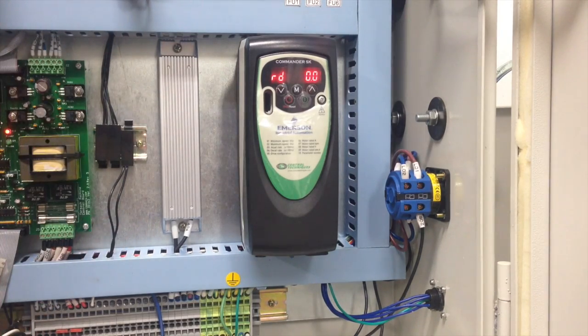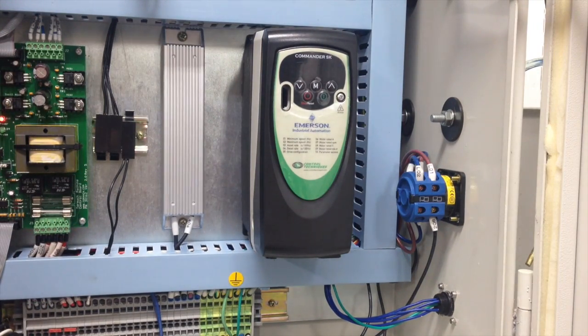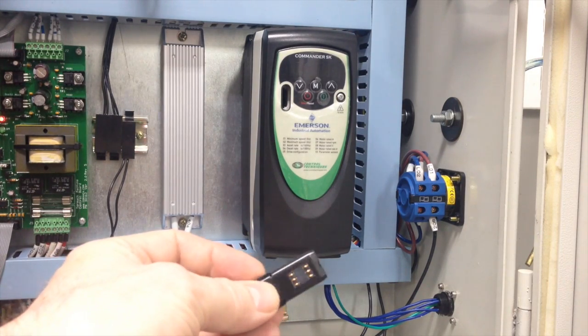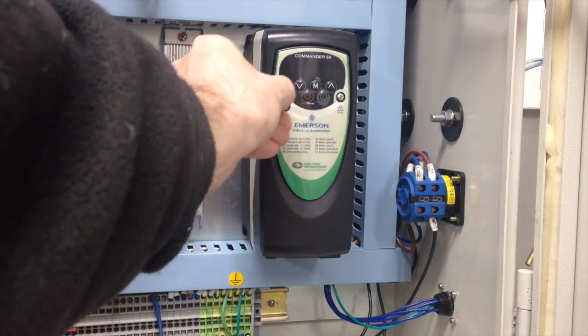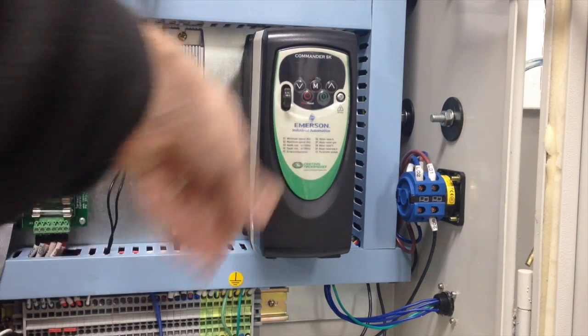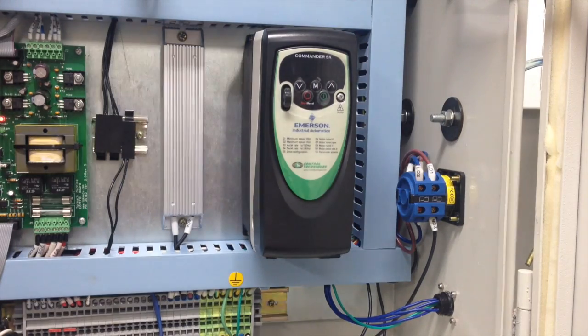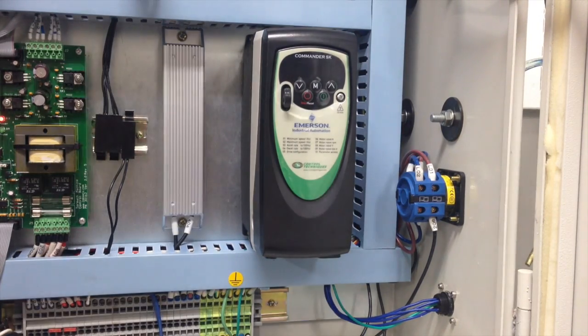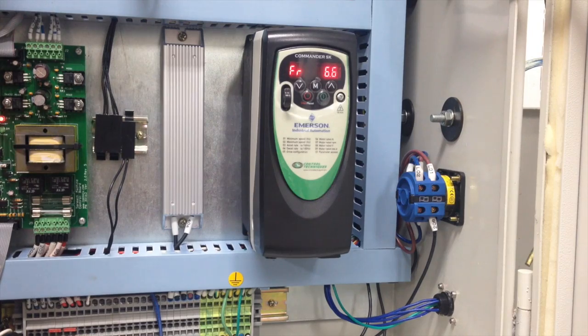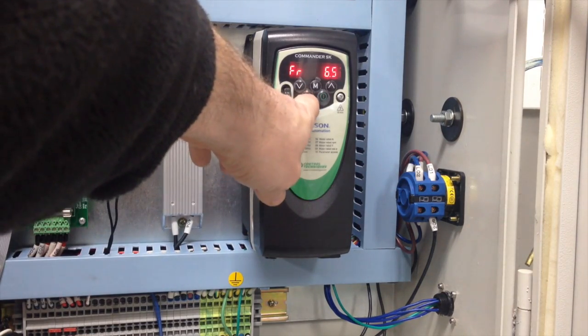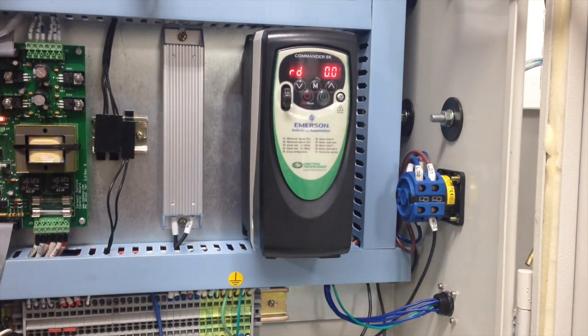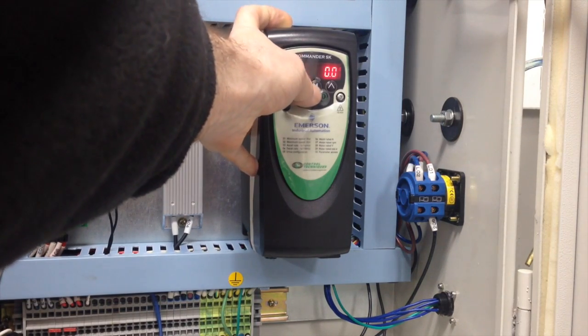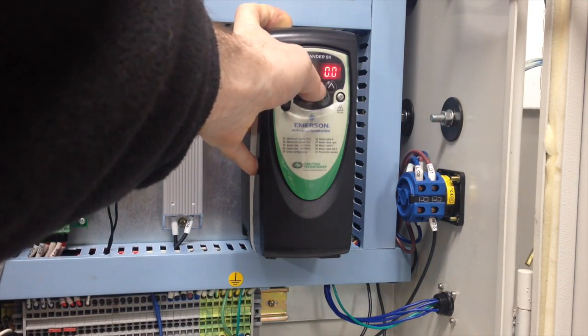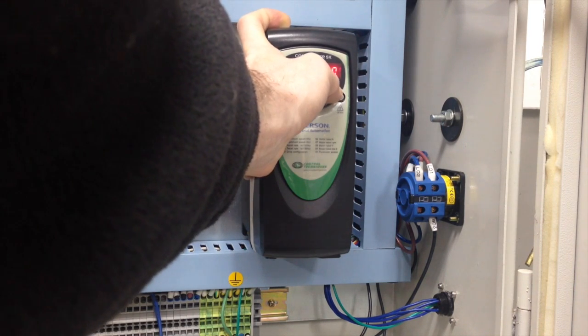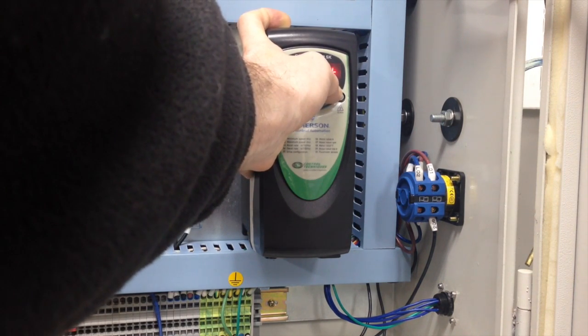Okay? Right, now we're going to do a parameter backup on the VFD. Take the smart stick. And the little metal contact should be placed to the left, put that in the slot on the front, and power the drive back on. You can stop the spindle again, red button. Okay, go into the menu structure by pressing M, and scroll up till you get to parameter 28.